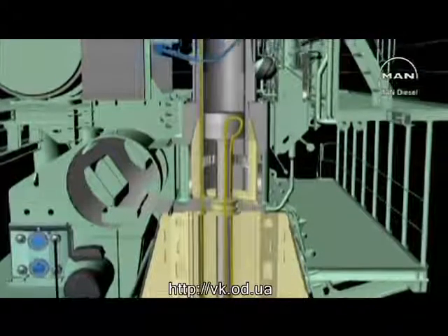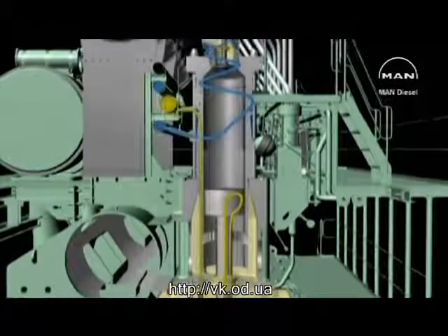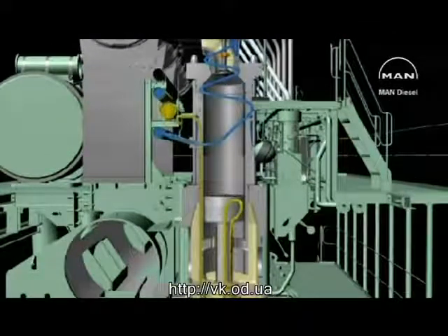This is possible because there's a drop in temperature as the heat passes from cylinder gas to metal. Even though the gas is in violent motion inside the cylinder, the boundary layer close to the wall forms a rather effective insulating layer where the temperature falls rapidly. Through the wall itself, the temperature falls evenly, but the heat transfer to the cooling water is controlled by the local boiling point of the water in contact with the wall, the so-called micro-boiling phenomenon.